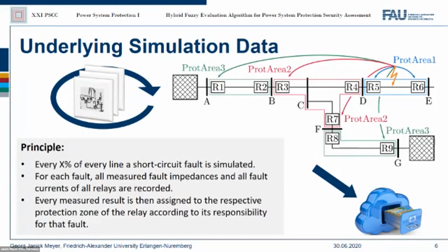Let's take a closer look at the diagram. We can see that a fault occurs on line DE. Directly connected and therefore responsible for that fault are the protection relays R5 and R6. So these relays store the simulation result in their own protection area 1 list. The backup relays R3 and R7 see the fault in the forward direction and store the measurement result in their protection area 2 list. The relays R1 and R9 provide backup for the relays R3 and R7 and store their values in their protection area 3 list.